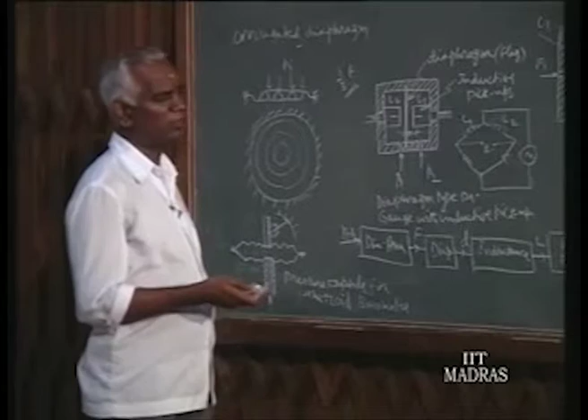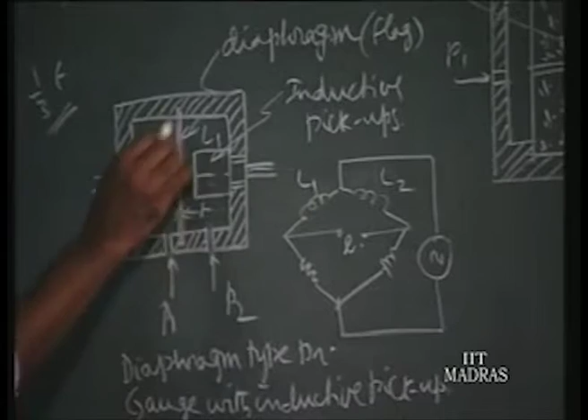How inductance and capacitance are made use of in sensing the deflection of the diaphragm is illustrated in the following diagrams. Here we have two inductive pickups, self inductance pickups, and this is the diaphragm, and the pressure difference P1 and P2 are allowed to act in this chamber. P1 being higher than P2, the diaphragm will deform in this fashion.